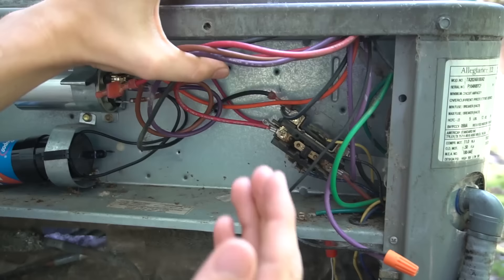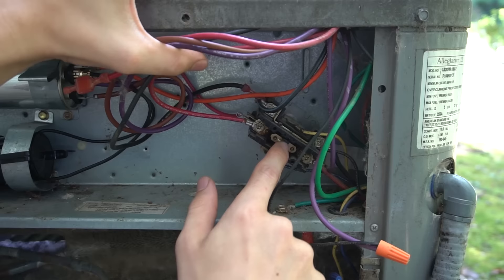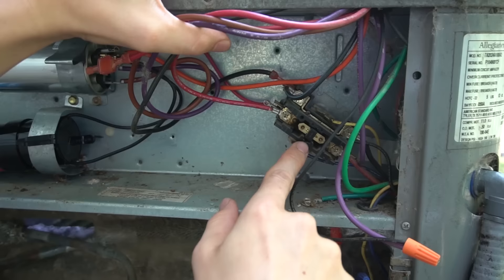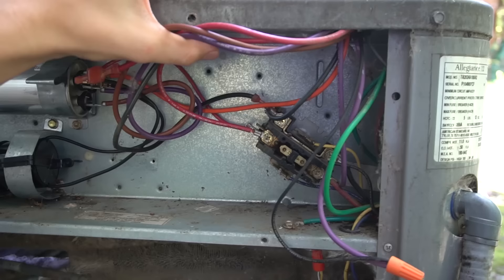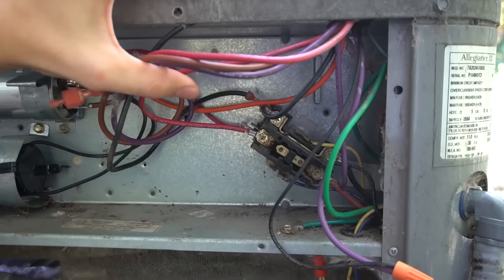Going back to the contactor — this is a relay, a control relay. It controls when the air conditioner comes on and off. 240 volts comes into the contactor, and the thermostat controls the little plunger. Right now the plunger is pulled in because my thermostat is calling for cooling — if the disconnect plug weren't out, my unit would be running. When the thermostat calls for cooling it sends 24 volts to the coil, pulls the contactor in, and that allows power through to turn on the unit. Two-stage condenser units sometimes have two contactors.